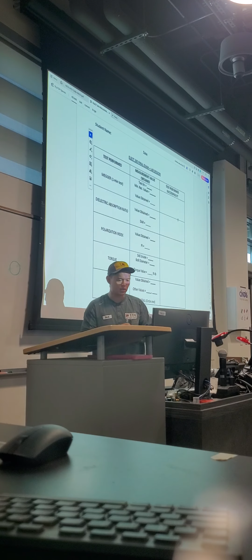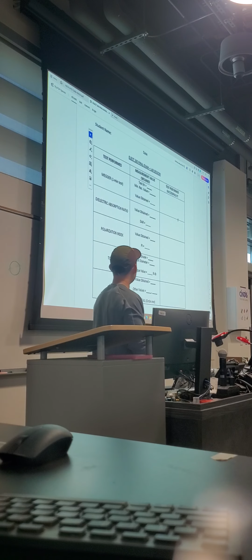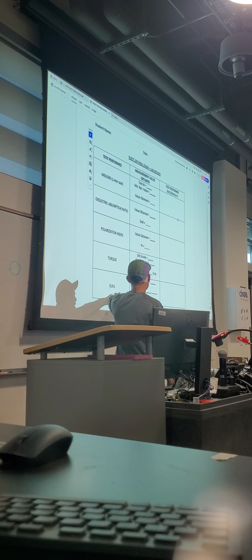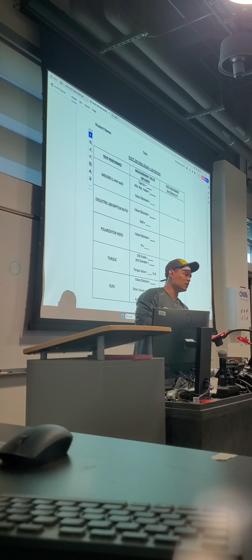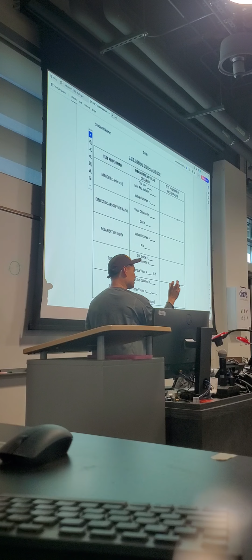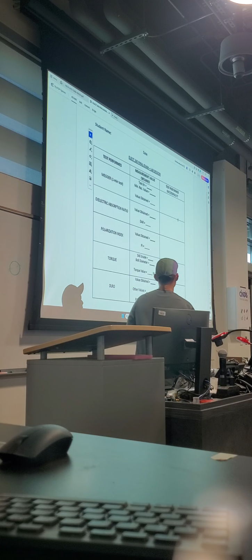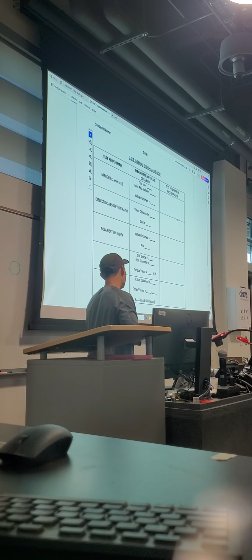So cable set 3 kind of stumbled in late for the class. Didn't come early as he was encouraged. And this person had highly suspect DLRO values. As they were clicking through, they subjected it to 0.1 amps, when really they could have gotten a much better reading had they subjected it to that 10 amp scale, right? Would have got better resolution on that reading. So he gives his group members suspect data, right? Remember, garbage in, garbage out.